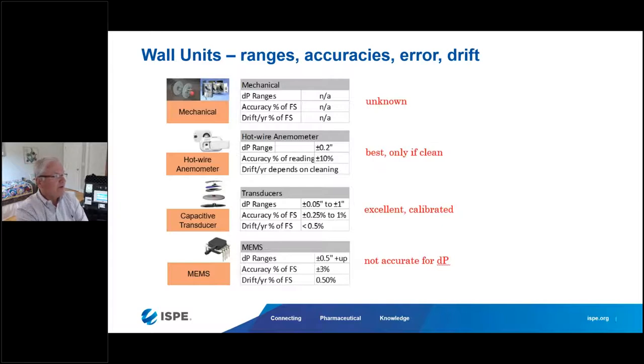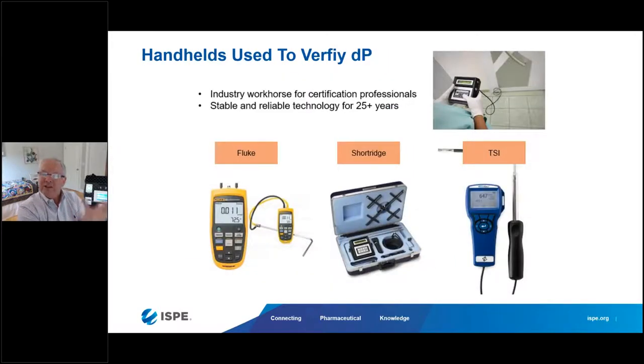These are excellent types of devices but do require maintenance and recalibration depending on the application. Some applications can be tolerant of just the drift characteristics; others are more stringent and would require annual or semi-annual recalibration. MEMS — micro-electro-mechanical systems — are not necessarily accurate enough today for differential pressure but can be used in duct static pressure applications.